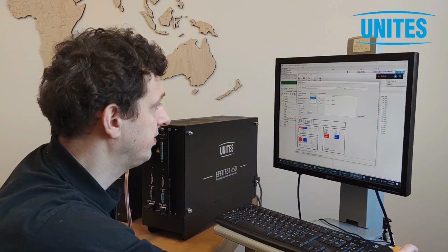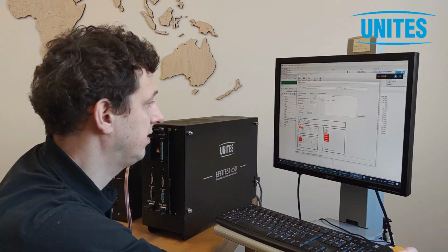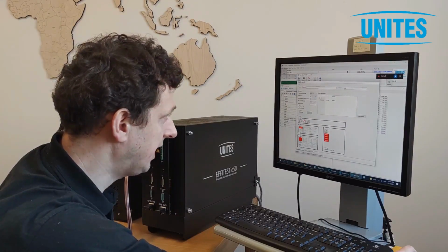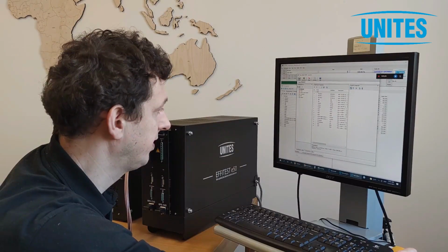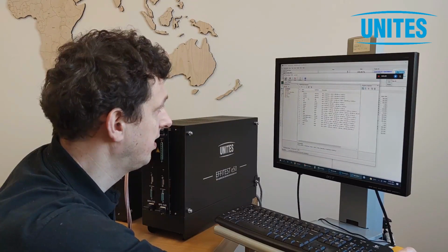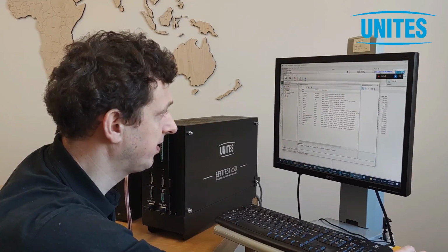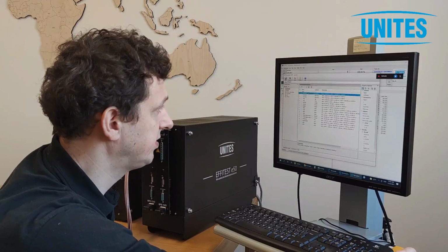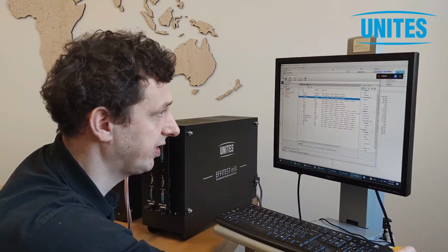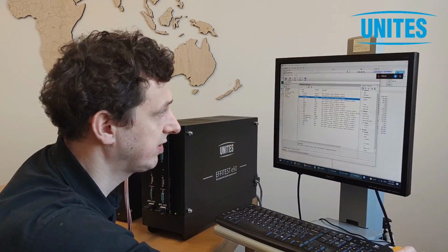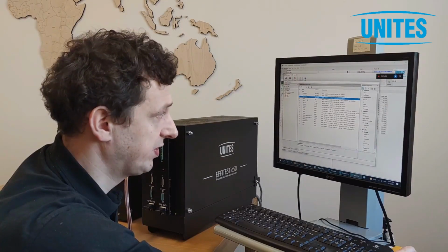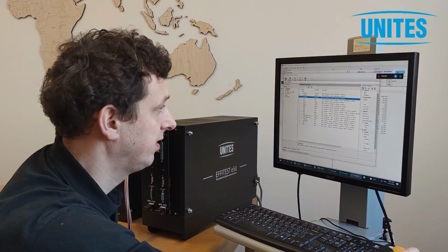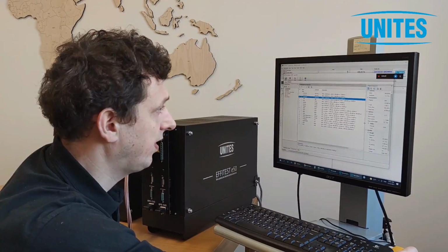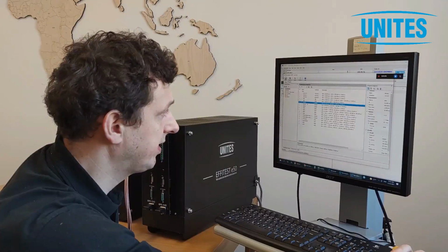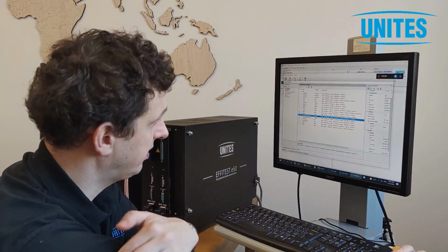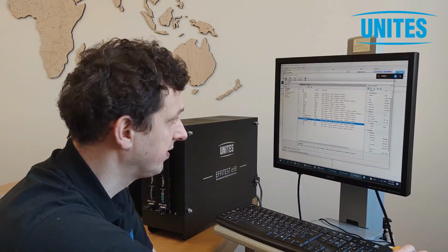Right now I will leave it to just one side, one test position to keep it simple, and then I will move to another tab which is called program. I can see my test program here. This is actually test program constructed from the datasheet. As you can see, the first 3 test steps are just checking the Kelvin measurement. It's checking if there is a component or not, if the component is present in the test socket or in the test position. Other test steps are VBE, VBC, breakdowns, currents, saturation voltages, and gain HFE.